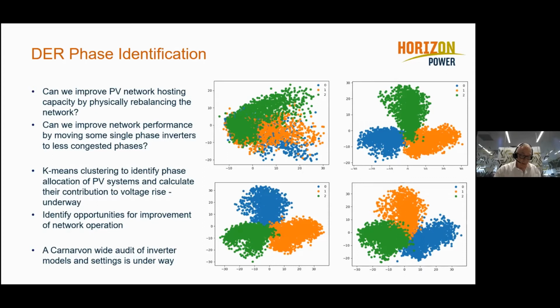So we've begun to explore if it's possible to improve power system performance by physically rebalancing the network through reallocation of single-phase PV systems to other less congested phases. Firstly, the application of k-means clustering analysis to advanced meter data is being used to identify the phase allocation of single-phase PV systems, and how much they are contributing to these overvoltage events. And then we're developing a strategy to move them to other phases so that we can reduce the load on those overloaded phases. When I say overloaded, I mean overloaded because of PV exports.